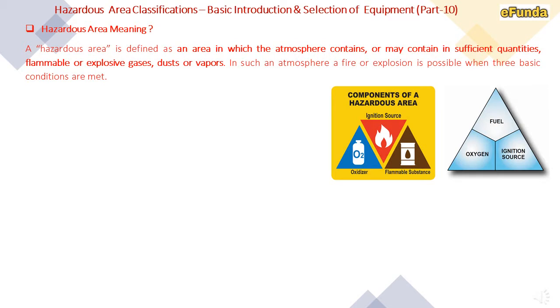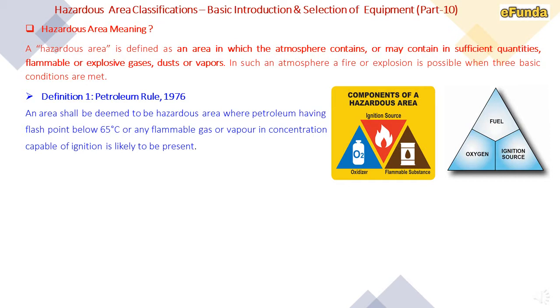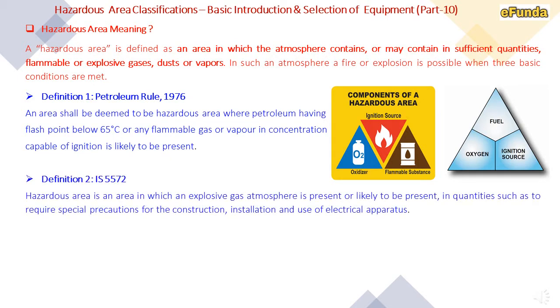Moving to the definitions of hazardous area. Definition 1 — Petroleum Rule 1976: an area shall be deemed hazardous where petroleum having a flash point below 65°C or any flammable gas or vapour in a concentration capable of ignition is likely to be present. Definition 2 — IS 5572: a hazardous area is an area in which an explosive gas atmosphere is present or likely to be present in quantities requiring special precautions for construction, installation and use of electrical apparatus.